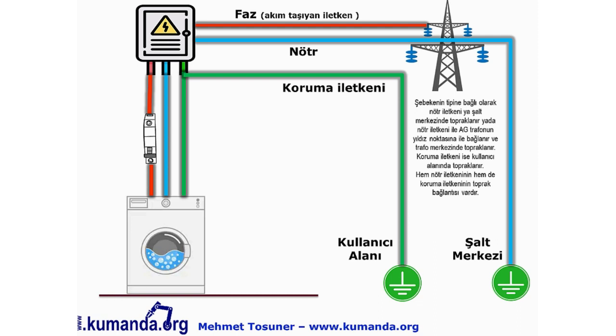Hem nötr iletkeninin hem de koruma iletkeninin toprak bağlantısı vardır. Şebeke bize faz ve nötür verir. TT şebekede şant merkezinde nötr iletkeni topraklanır; TN şebekede ise AG dağıtım trafosunun sekonderi yıldız noktasıyla birlikte topraklanır. Koruma iletkenimiz ise kullanıcı alanında, örneğin binaya çakılan topraklama kazıklarıyla toprağa verilir.